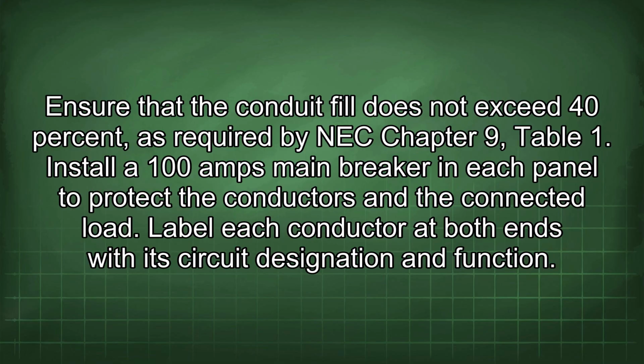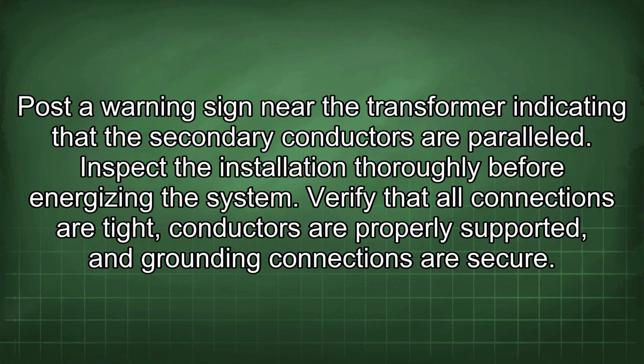Install a 100 amps main breaker in each panel to protect the conductors and the connected load. Label each conductor at both ends with its circuit designation and function. Post a warning sign near the transformer indicating that the secondary conductors are paralleled. Inspect the installation thoroughly before energizing the system. Verify that all connections are tight, conductors are properly supported, and grounding connections are secure.